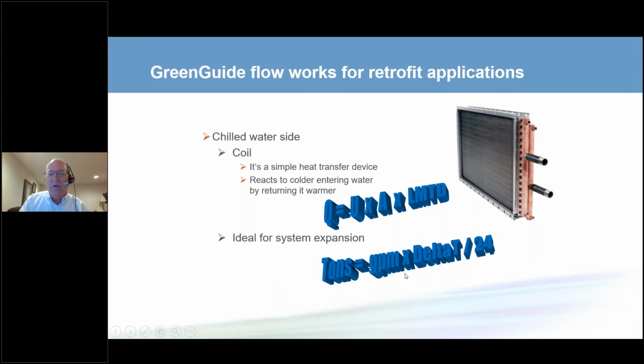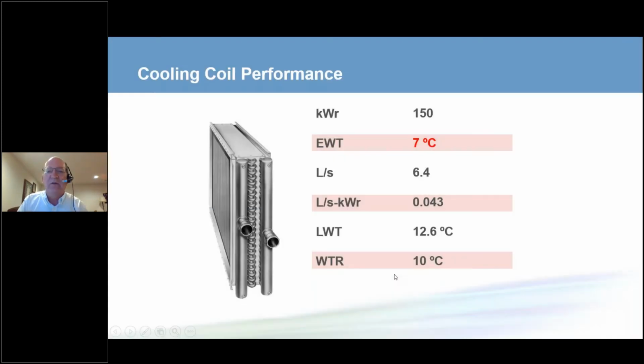So let's look at an actual coil selection. And this is an existing air handling coil. So the goal in this case was to deliver after the retrofit the same leaving air conditions and therefore the same load. In order to do that, the coil was reselected. Instead of using a 7-degree entering chilled water temperature, it uses a 5-degree C temperature. The flow rate goes down by just under 40%.